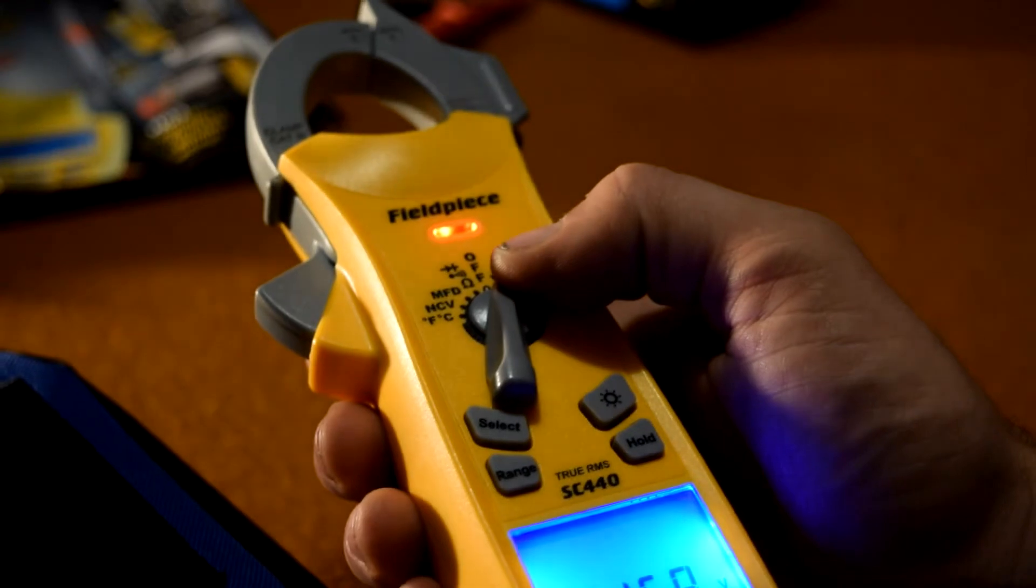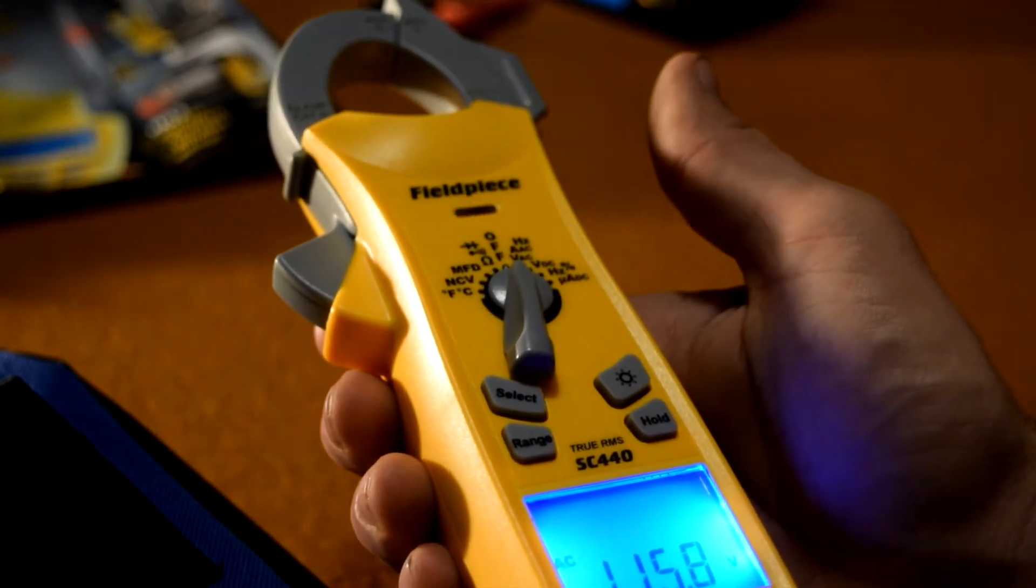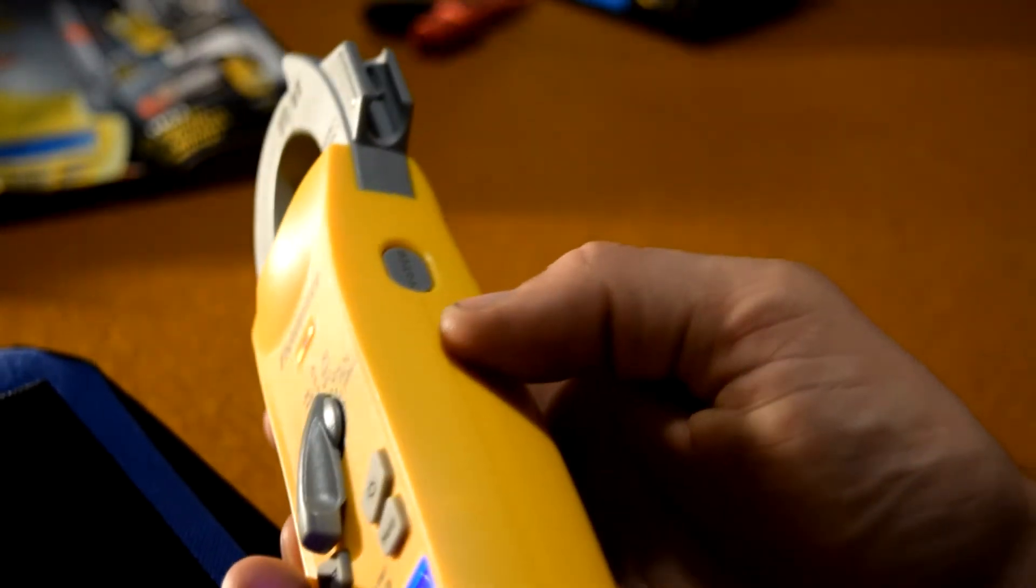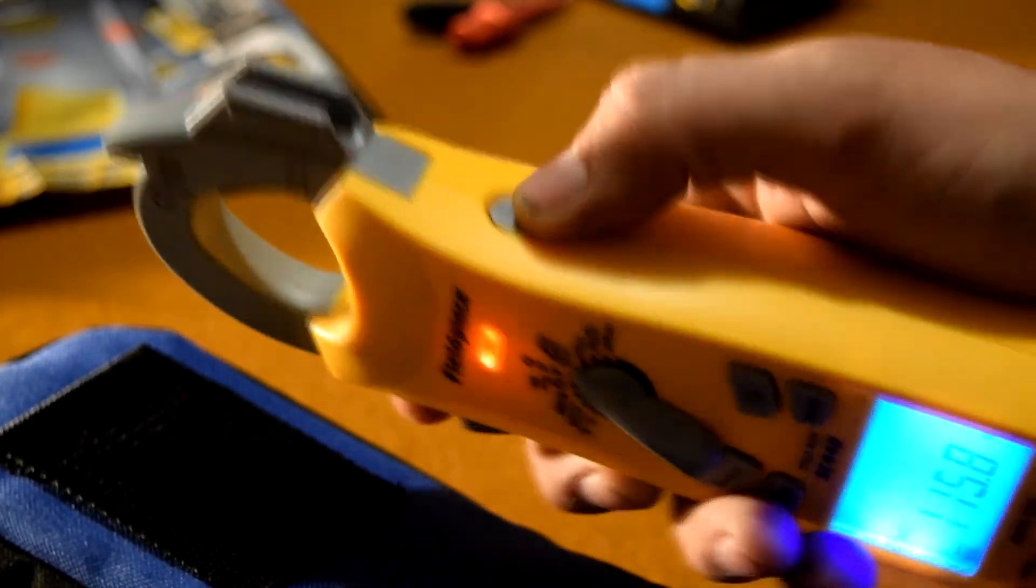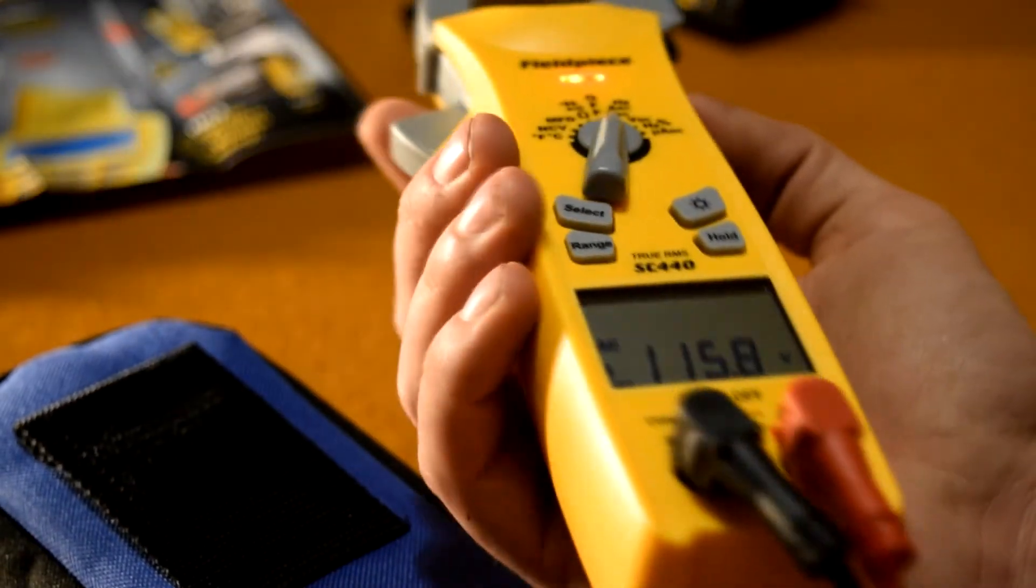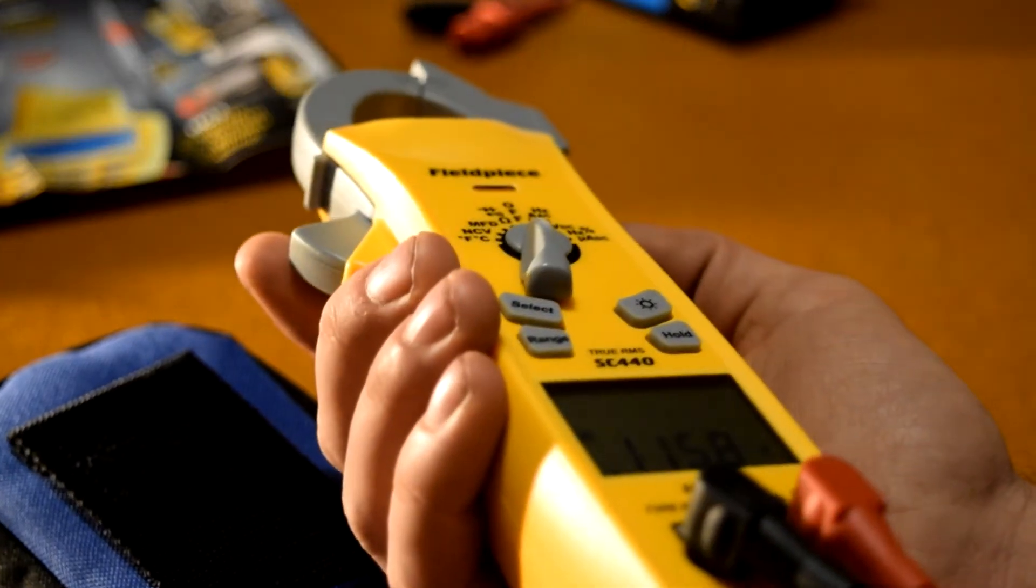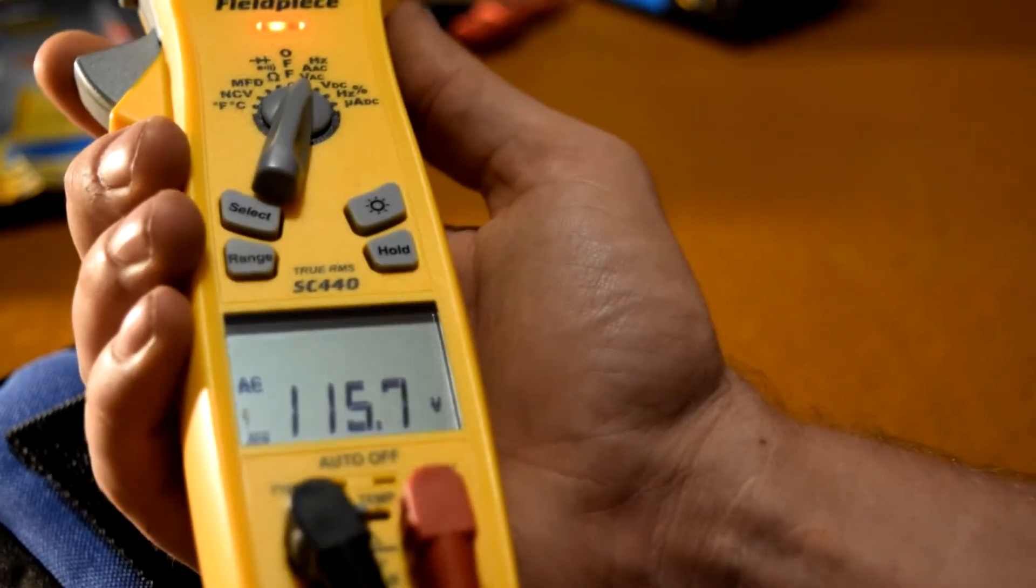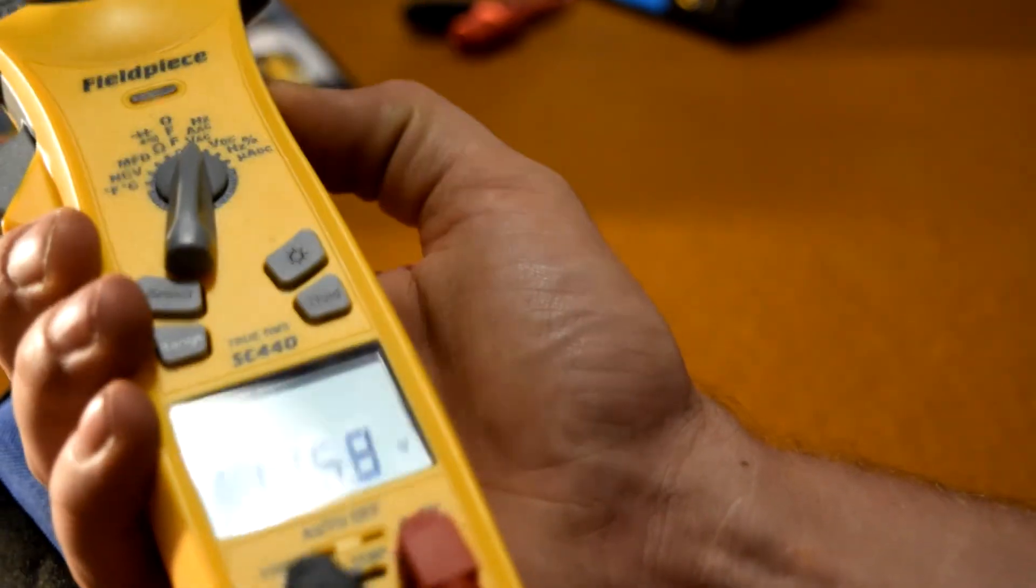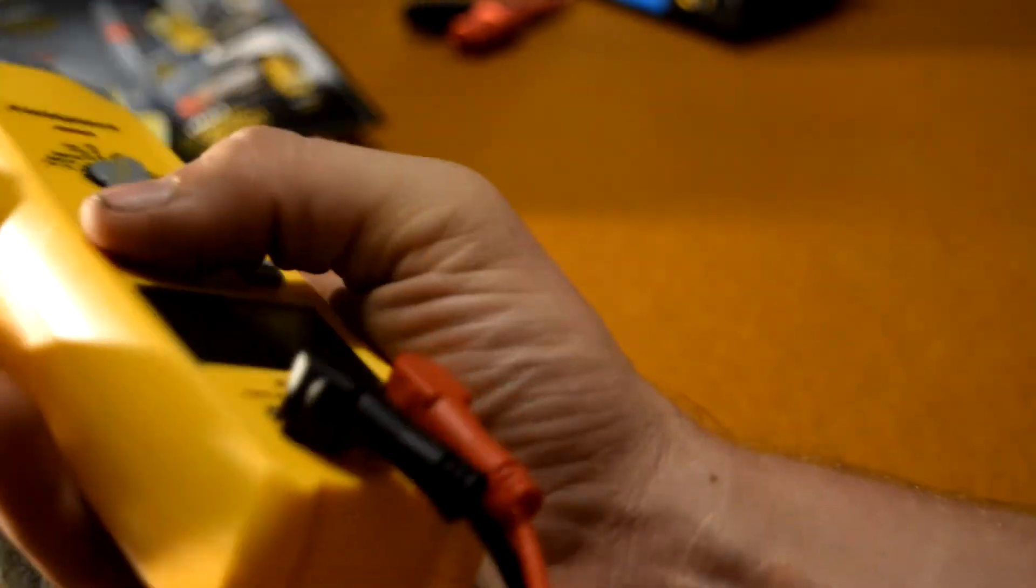What's cool about this, it gives you a flashing light and a beep in case there's electricity. Now inrush - you can see that right there - this button here is to find out the load, the high load of something. So I can find out how many amps is coming through a compressor by holding this button down during an amp test.